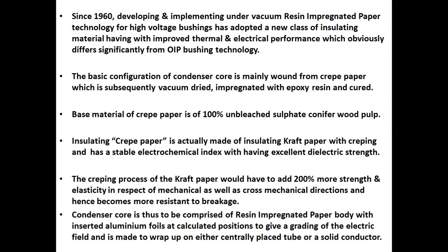The condenser core is thus comprised of a resin impregnated paper body with inserted aluminum foils at calculated positions to give a grading of the electric field, and is wrapped on either a centrally placed tube or a solid conductor.